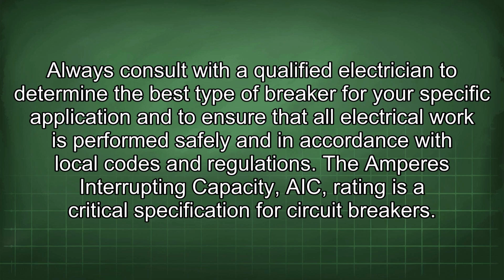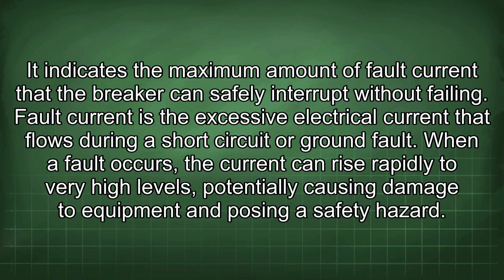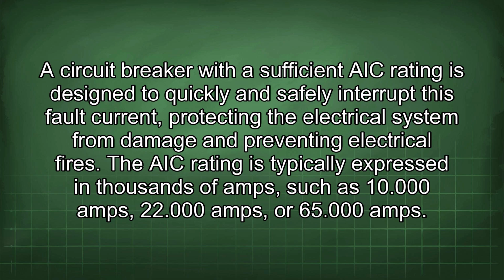The amperes interrupting capacity (AIC) rating is a critical specification for circuit breakers. It indicates the maximum amount of fault current that the breaker can safely interrupt without failing. Fault current is the excessive electrical current that flows during a short circuit or ground fault. When a fault occurs, the current can rise rapidly to very high levels, potentially causing damage to equipment and posing a safety hazard. A circuit breaker with a sufficient AIC rating is designed to quickly and safely interrupt this fault current, protecting the electrical system from damage and preventing electrical fires.